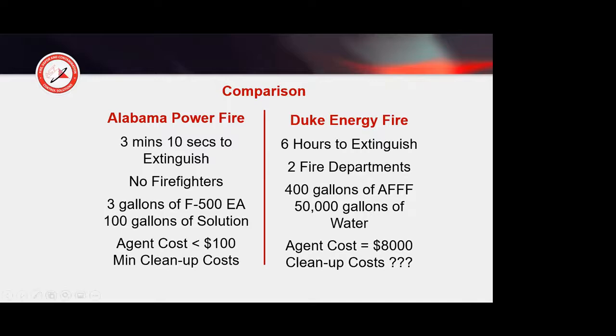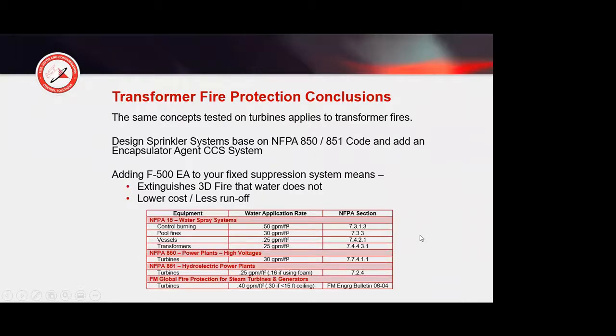This is a comparison between the Alabama Power and Duke. Duke was a 6-hour extinguishment with 2 fire departments, 400 gallons of AFFF, 50,000 gallons of water. So just the agent cost at 20 bucks a gallon was 8,000. I can imagine what their cleanup costs were. So for transformer fire protection, again, the code's really designed to just control the fire with plain water. The F500, adding it is suppressing the fires.